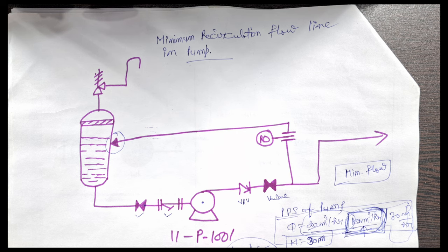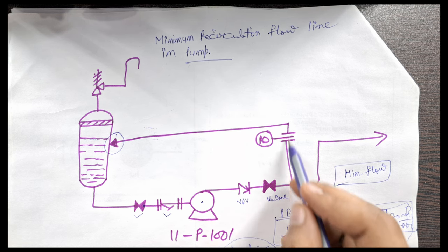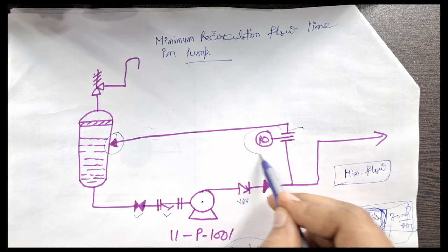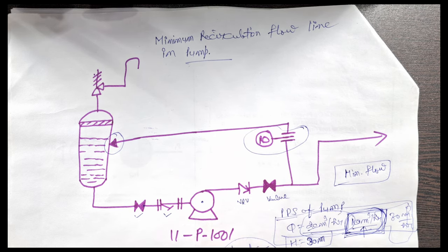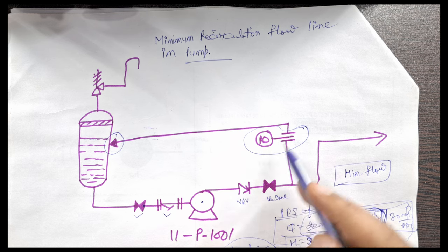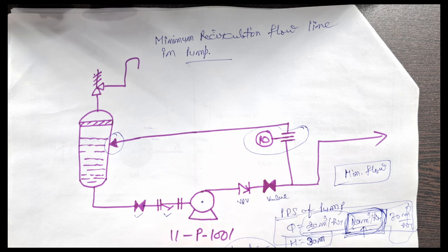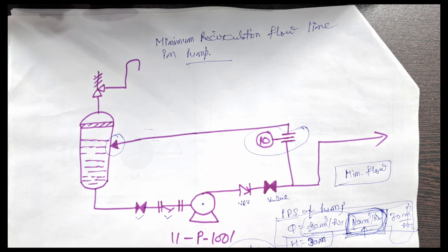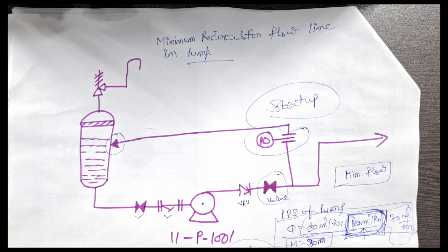What we do is provide one recirculation line back to the vessel, and in this line we provide an RO — a restriction orifice. Please let me know in the comments box why we provide this RO in the minimum recirculation line, and why we provide a valve or control valve in the recirculation line.